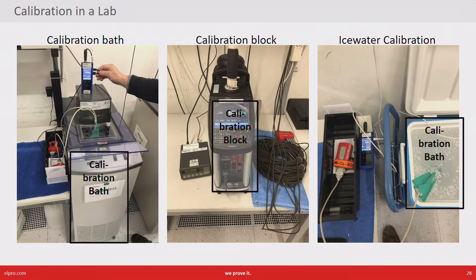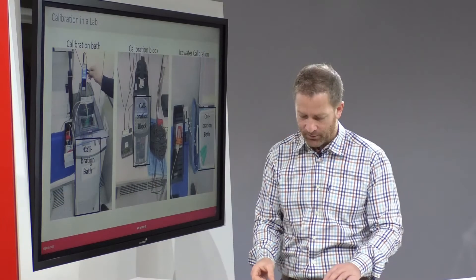The third example is the most simple and cheapest way of calibration: ice water. Ice water has the physical property that it is always exactly 0.00 degrees centigrade. Again, you can dip entire devices here because there is a lot of space inside this calibration bath.